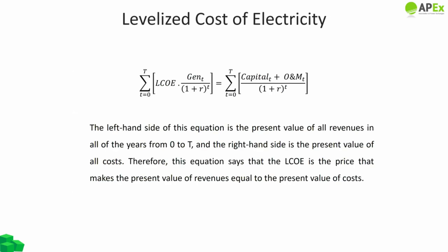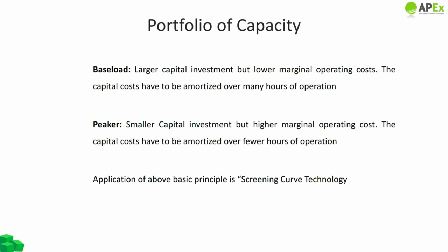The LCOE equation shown on screen states that the left-hand side represents the present value of all revenues over years zero to T over the life of the project, and the right-hand side is the present value of all costs. Therefore LCOE is the price that makes the present value of revenues equal to the present value of costs. To determine which types of capacity are most needed, we must look beyond the simplistic representation of LCOE. For example, how much of the capacity should be baseload and how much should be peakers, and how much intermediate generation capacity is needed.